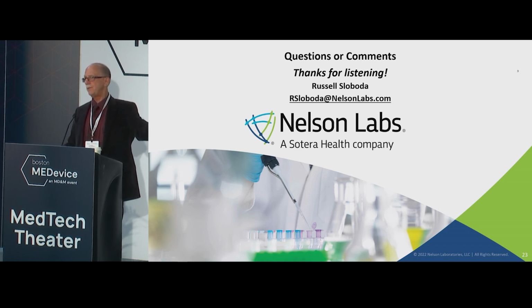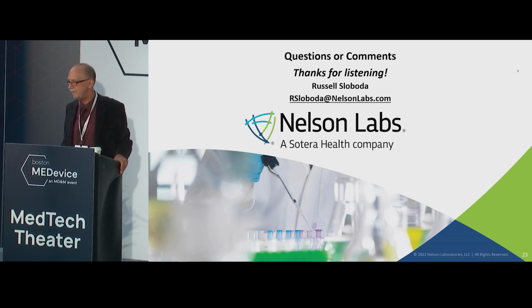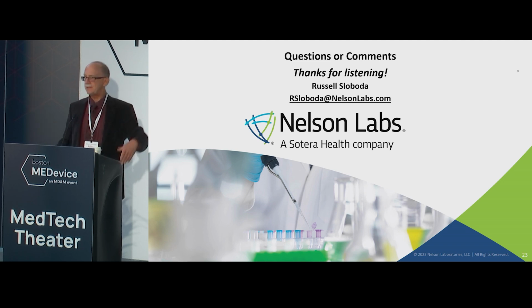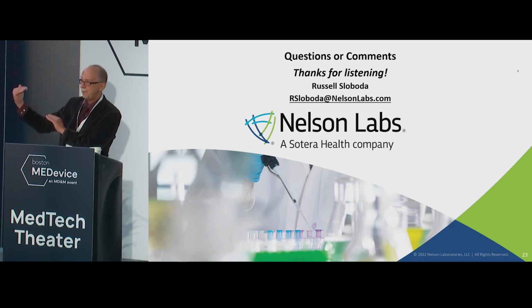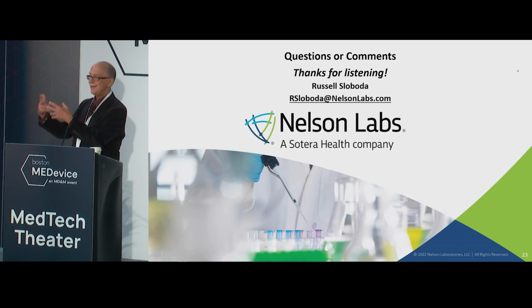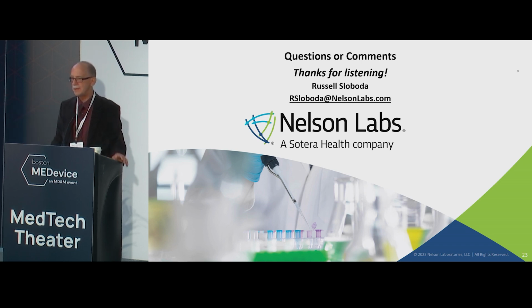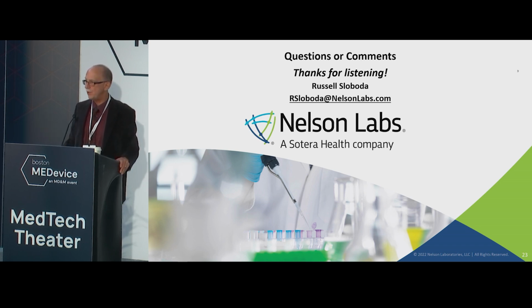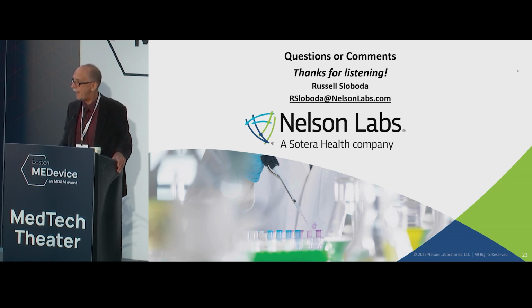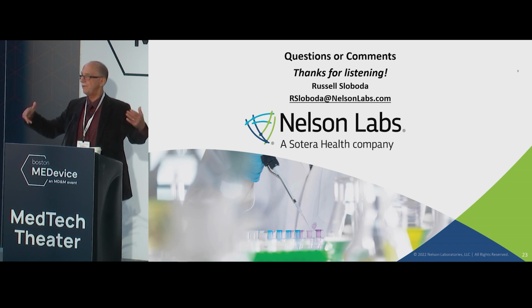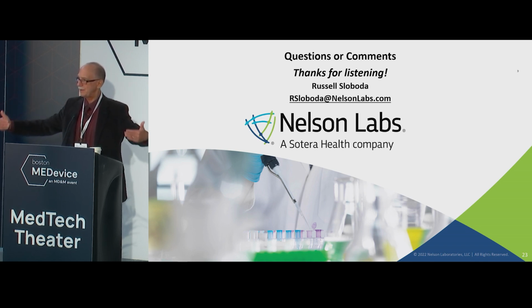For certain risks, like these high toxicity values, isocyanates, phthalates, very stringent thresholds, when you go to release kinetics, you lower the temperature and do 24-hour data points. Less is extracted each 24 hours. And by combining those approaches, you come up with an effective approach that very often does pass because there are several variables that are more realistic when you do it that way.